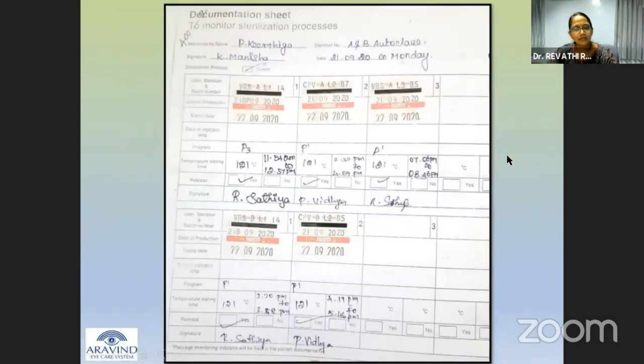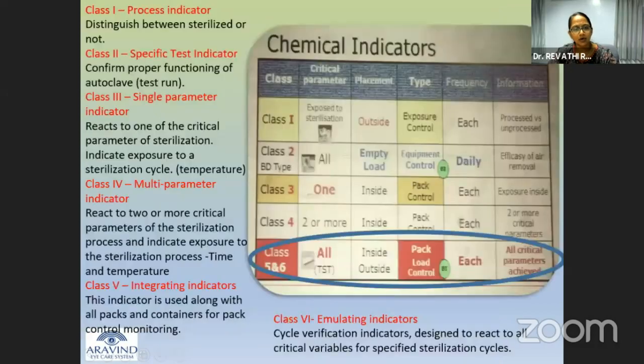But we have to keep in mind, though it is automated, every parameter has to be documented when it comes to the court of law. In a litigation process, you need to have documented that this process has gone through the standard phase with the temperature and what load. The three-label indicator gives us clear information: what load, how many instruments were put in, and what things were used for the patient. So this has to be clearly maintained in the autoclave record.